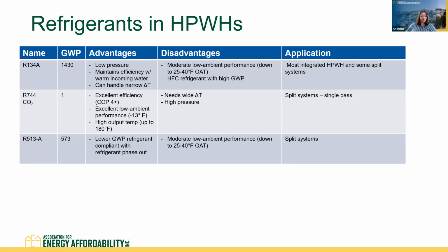In terms of refrigerants, I mentioned these heat pump water heaters use refrigerants to move heat around. There are a couple of common refrigerants for heat pump water heaters, and they have different characteristics and play into equipment options and choices, with different pros and cons. The ones you're going to see most regularly are R134a. That's going to be in most integrated heat pump water heaters, that unitary scale, and some split systems as well.